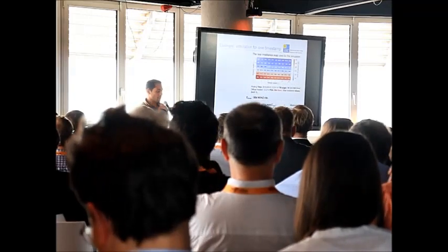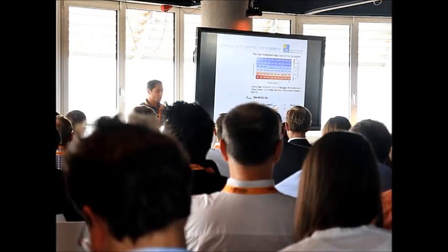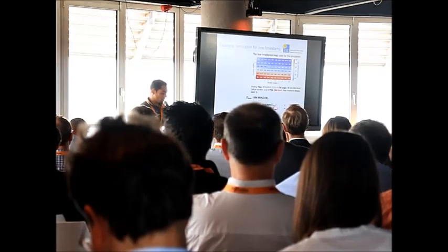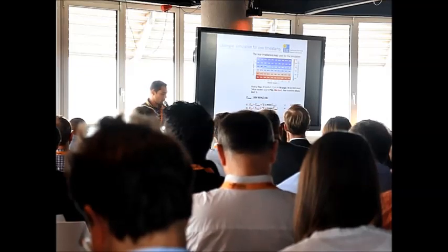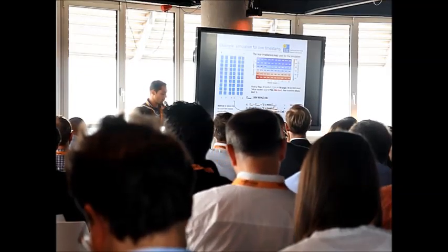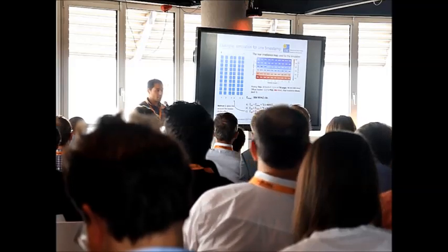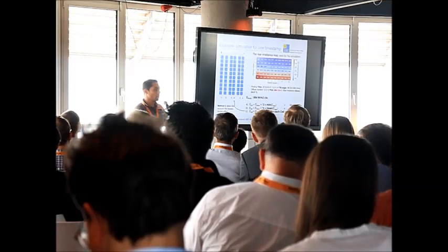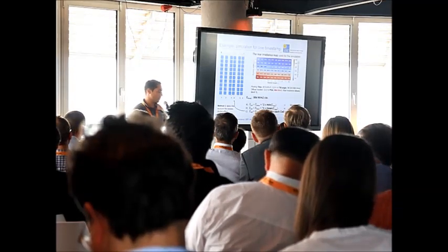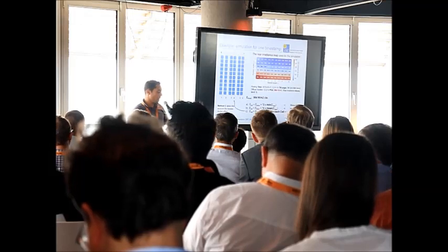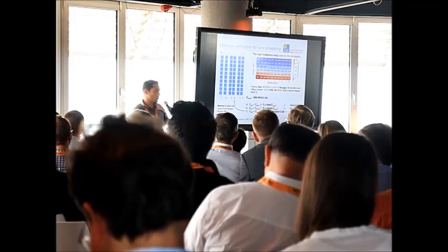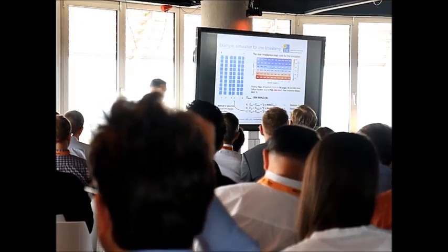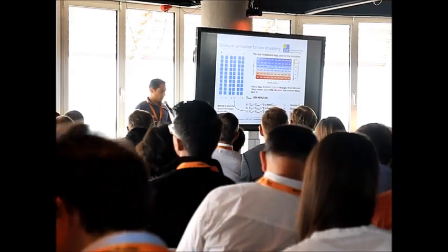So here is an example where I took the real irradiance map from this measuring device. And as I mentioned, I would use method A, which takes the minimum irradiance, and method B takes the mean irradiance. And method C actually needs to know also about the module: how many groups within the module, how many bypass diodes you have. And this is method C also. So this is additional information that is needed when I use method C, while methods A and B, which use the datasheet of the solar panel, do not need to know this information.